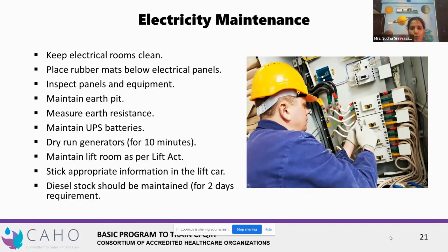Inspecting the panels and equipments periodically as part of the preventive maintenance is important. Maintaining the earth pit in the required frequency. The required frequency is at least once in 2 years. It's always a good practice to do it every year if you have high-end equipments like MRI, CT, PET CT, etc. Measuring the earth resistance is as important, because a lot of short circuits, if it is not measured properly, if it is not maintained properly, there could be a lot of fire hazards that can cause inside the hospital. Maintaining your UPS batteries is important.